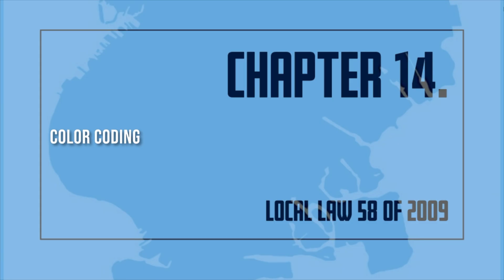Dedicated standpipe valve handles must be painted red. Combination standpipe valve handles must be painted yellow. Dedicated sprinkler valve handles must be painted green. Cutting and capping. Local Law 60 of 2009, effective the 2nd of March 2010. Permits are required to cut and cap standpipes or sprinklers.